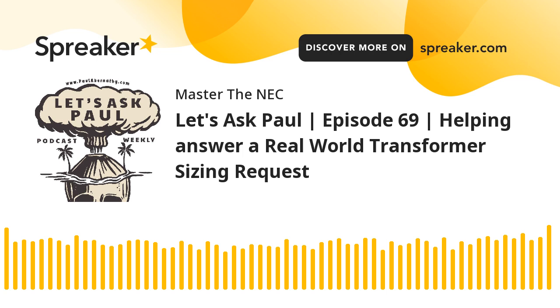Okay. Now, as far as the conductors, since I went to that overcurrent, we still have to protect those conductors at their ampacity, right? So I'm going to be terminating those conductors into whether it's a 45 amp device or a 70 amp device, okay? So I have to be sure that I have a conductor that's going to terminate and be adequately protected by terminating into those devices. So I'm going to go to 310.16 and I'm going to see if I can find me a conductor.